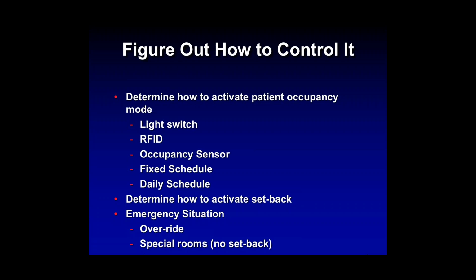Then you have the emergency situation where we had a concern, well, maybe emergent cases don't get put onto the schedule. And even though we've been assured that they all do, we felt that there should be an override and a user interface in those ORs. So we made sure that we did that. And then lastly, if they're still concerned about those emergent cases, you may have to set aside one of the rooms that they use for emergent cases and not put that on setback. Although that's not optimal, at least it gets you where you need to be, and maybe you can prove to them over time that the other system does work and convert that one as well. Next slide, please.